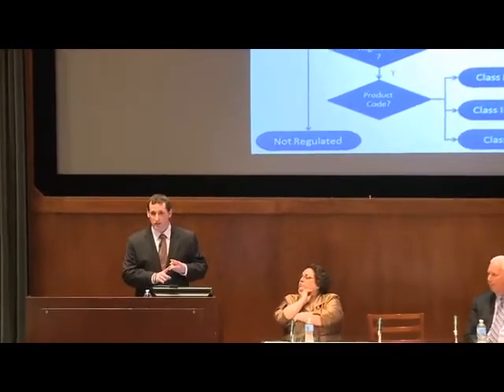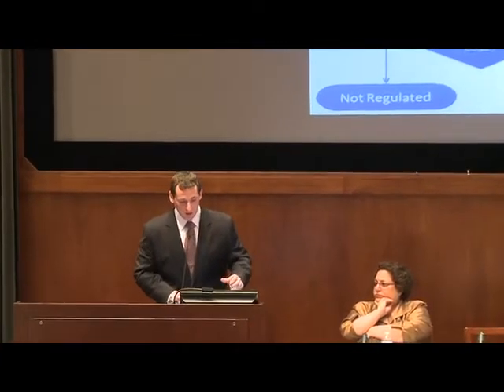List, 510K, or PMA. There's also a fourth thing here, included because it's becoming very important: the de novo review. This means all unknown devices start out as class 3, requiring a PMA. But FDA realizes some devices look very similar to existing devices, even though there wasn't something else to compare it to. For those, if you're initially class 3, you can go through this de novo process. In proposed guidance this might become almost a fourth classification, where you go through a classification stage and then file your 510K.